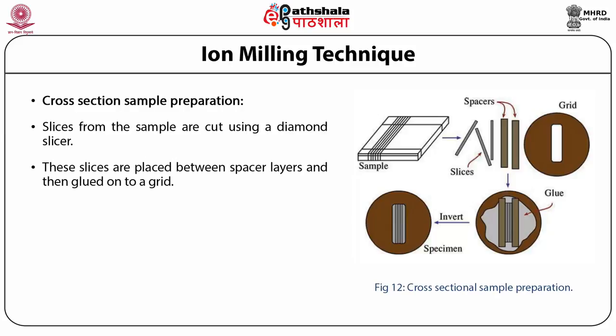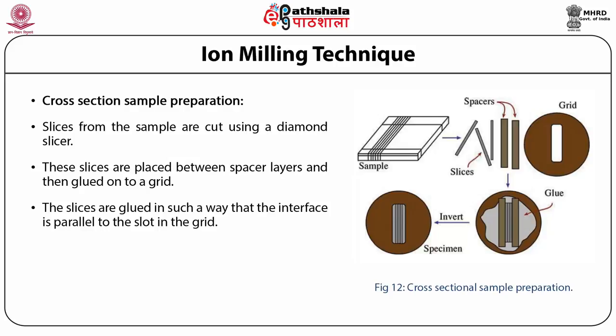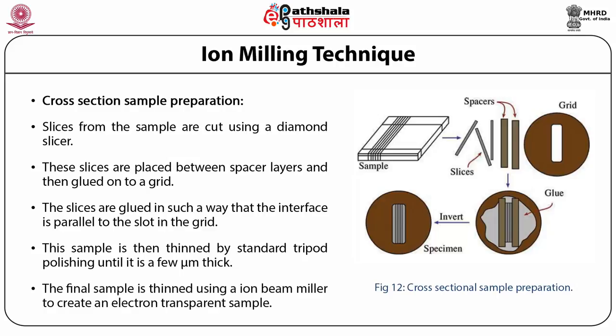The third technique is cross section sample preparation. Slices are cut from the sample using a diamond slicer, placed between spacer layers, and glued onto a grid so that the interface is parallel to the slot in the grid. The sample is then thinned by standard tripod polishing until it is a few microns thick, and the final sample is thinned using an ion beam miller to create an electron-transparent sample.